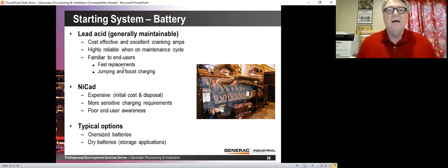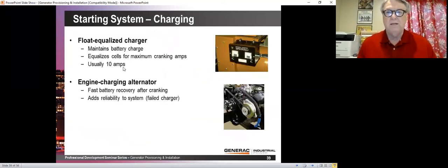Lead acid batteries are typical. NiCad, people experimented with those a ways back, but nobody uses those anymore on generators. Some people feel like lithium batteries may move into the generator field, but we have not seen them. So with engineers and with customers, it's just standard to use lead acid battery. Should have a float equalized charger. We like the 10 amp charger.